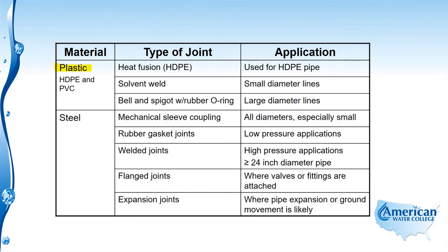Next is the plastic type of joint. When we talk about plastic pipe, we're talking about HDPE and PVC. For HDPE — high-density polyethylene — pipe, heat fusion is the type of joint used. For PVC pipe, solvent welds are used only on small diameter lines, and for larger diameter PVC pipe we use bell and spigot with rubber O-rings.